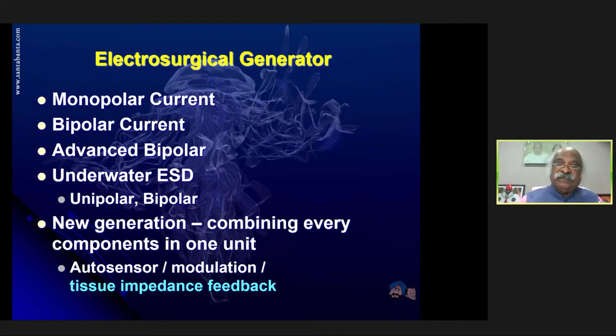Every tissue has a resistance, and the resistance varies from one tissue to another. For example, in scar tissue the resistance is much more, in adipose tissue it is medium, and in vessels, where fluid is present, resistance is least. Therefore the tissue impedance varies from one tissue to another. There is a system in the machine to know the tissue resistance, the tissue impedance feedback, and accordingly it auto-modulates and sends the current, which can be really rewarding for the surgical endeavor and electrosurgical principles. Now, let us understand what is a monopolar, what is a bipolar, what is a vessel sealer, and what is underwater cautery.